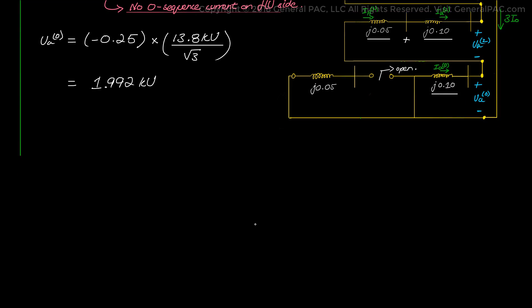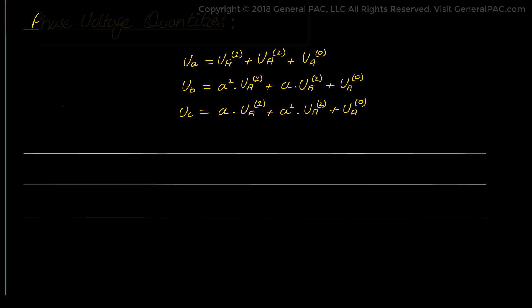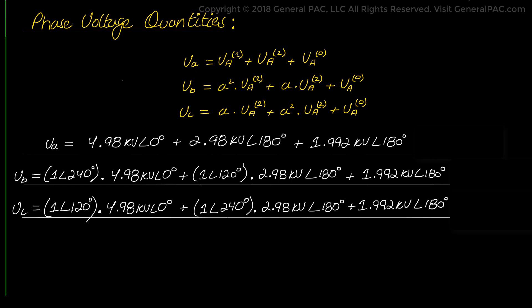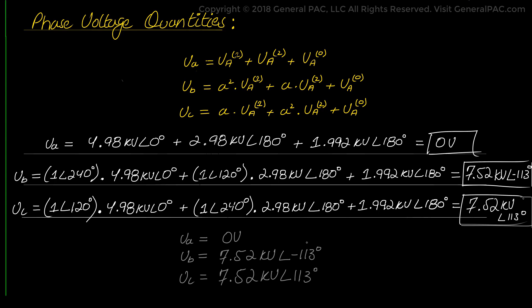Now that we've calculated all three sequence voltage quantities — positive, negative, and zero — we use the familiar transformation equations to get the phase voltage quantities at the point of the fault on the 13.8 kV bus. Plugging in the three sequence components and the A operator and solving with a scientific calculator: the voltage at phase A equals 0 kV, the voltage at phase B equals 7.52 kV at negative 113 degrees, and the voltage at phase C equals 7.52 kV at positive 113 degrees.